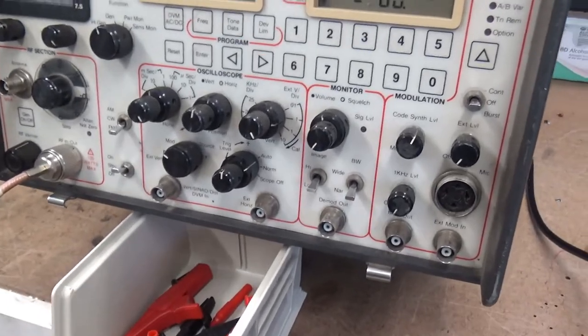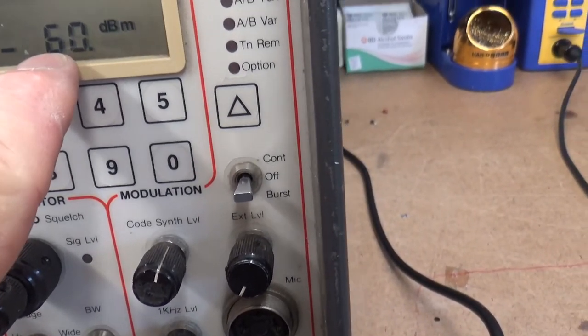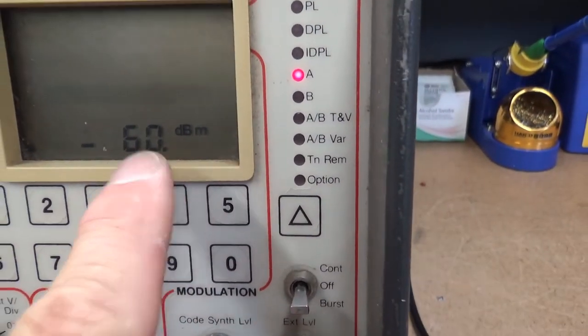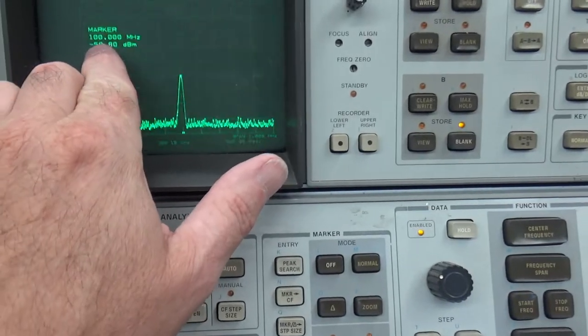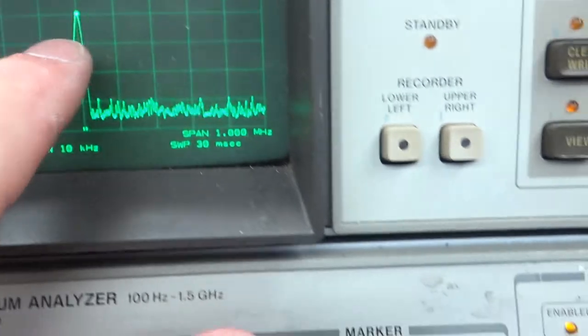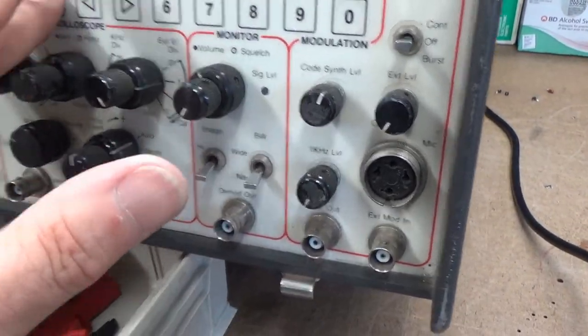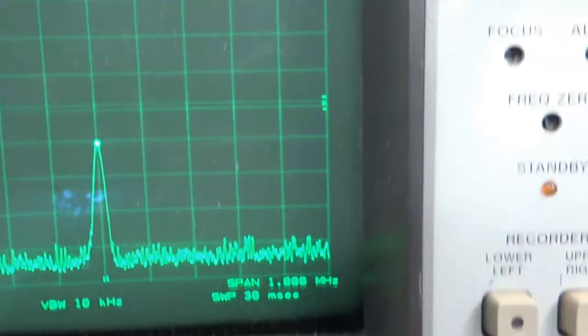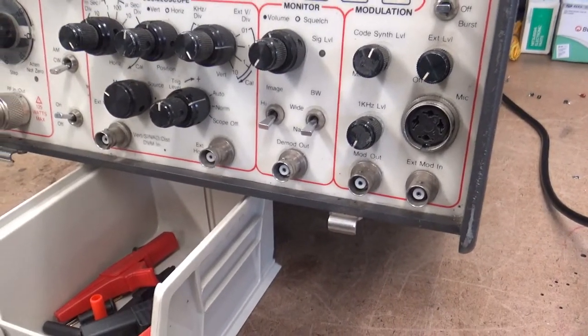On the generate section, I've set it for minus 60 dBm at 100 MHz. The marker reads minus 59.7 - going through cable loss so there's a little error, but it's pretty much right on. Going to 800 MHz, still at minus 60, fluctuating around minus 60.7 - that is fine, nothing wrong with that. High-gen is working, mod seems to be good.